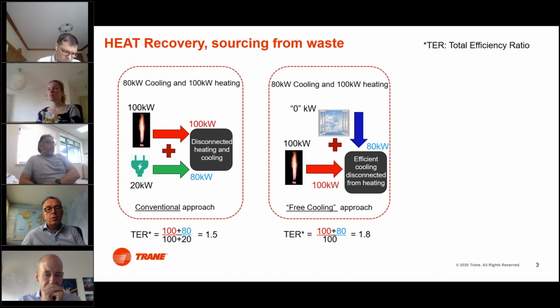And by the way, I did not mention it yet, but TER stands for the total efficiency ratio. In fact, it's a ratio between the energy creation for use of heating and cooling and the energy consumption for that heating and cooling. So the energy consumption for cooling gets reduced when free cooling kicks in.